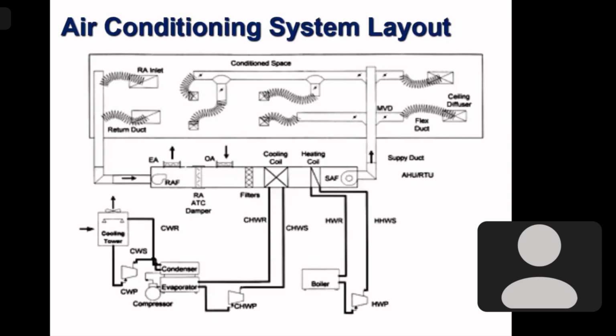This is the complete air conditioning system. So you just see the bottom left corner where we have a compressor. From the compressor, the refrigerant goes to a condenser. The condenser is cooled by a condenser water pump, which supplies water from the cooling tower, and the water is taken back from the condenser to the cooling tower.